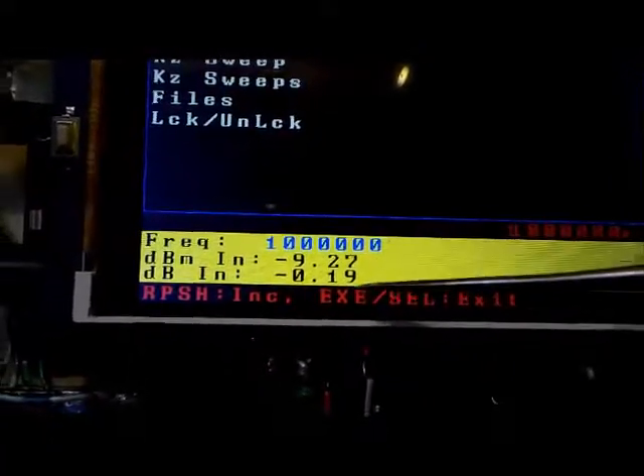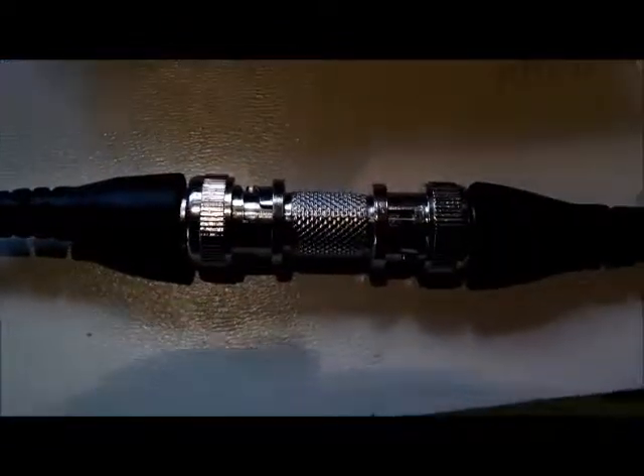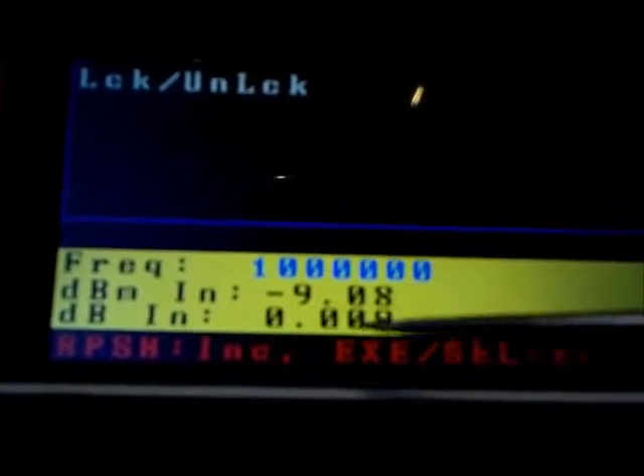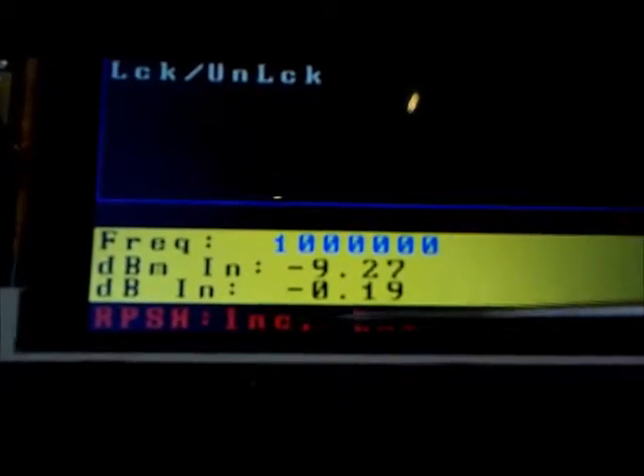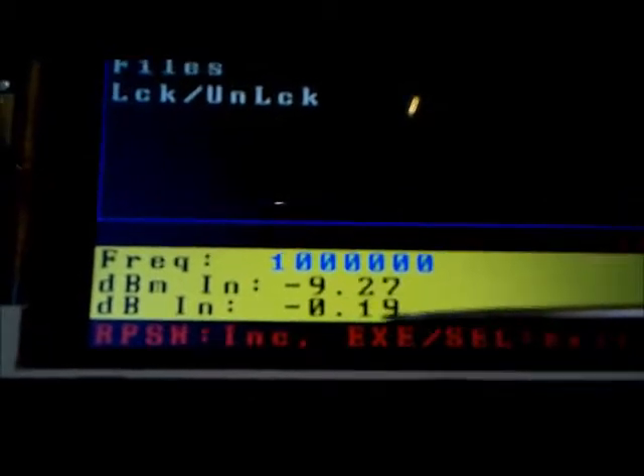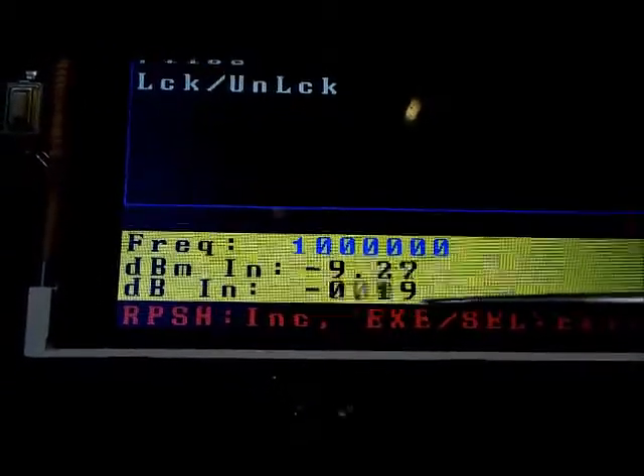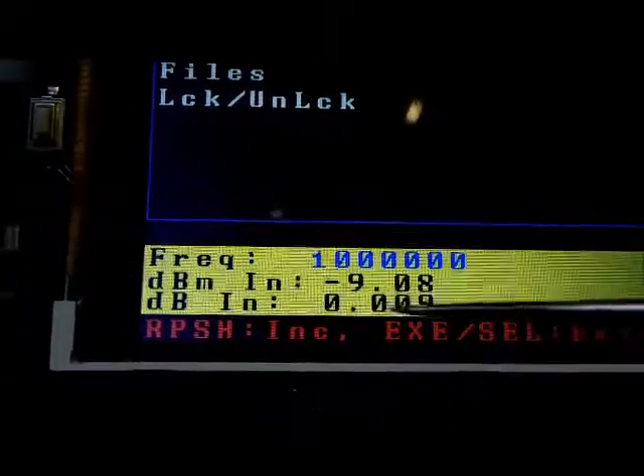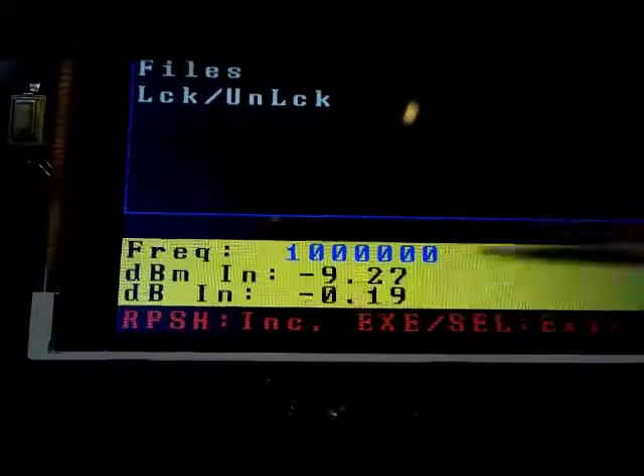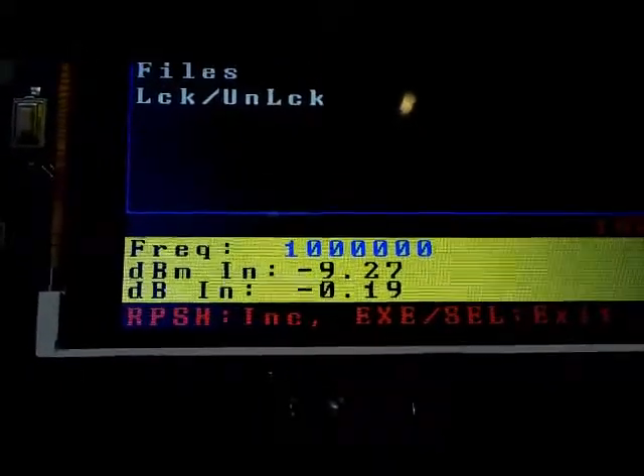So in this case, I have got a barrel connector connected, and as expected, we're seeing about zero dB loss. The dB in is basically giving you the loss across that barrel connector. So we're seeing less than 1 dB of loss across that connector.